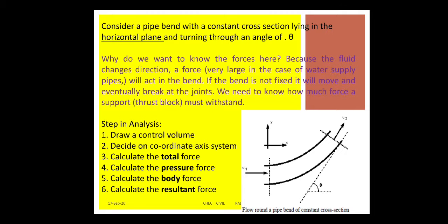So what are the things you have to find out? We have to know the forces here. Why do we want to know the forces? Because the fluid changes direction, from the horizontal axis to the vertical axis. Whenever the fluid changes direction, the force also changes. A very large force, in the case of water supply pipes, will act in the bend. If the bend is not fixed, it will move and eventually break the joints.